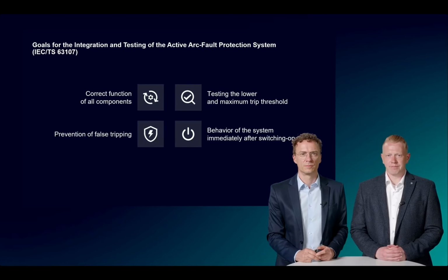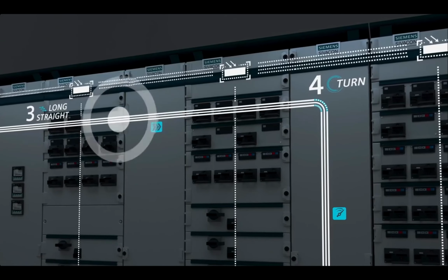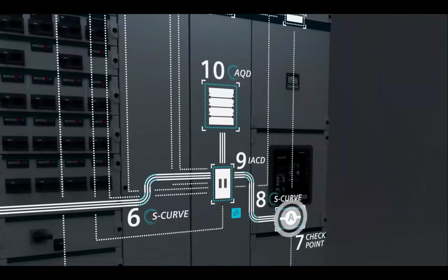Now let's take a look at how the active arc fault protection works. With an arc fault, especially in distribution systems, a flash of light is created, which is detected by an optical sensor. Simultaneously, current transformers detect a rapid surge in current. Both are relied on by the IACD detection device. When both a flash of light and a current surge happen at the same time, it is identified as an arc fault incident. But that refers only to phase to phase faults. The reduction of energy releases does not influence the short circuit current in case of a phase-to-phase fault. And you can do even more things.